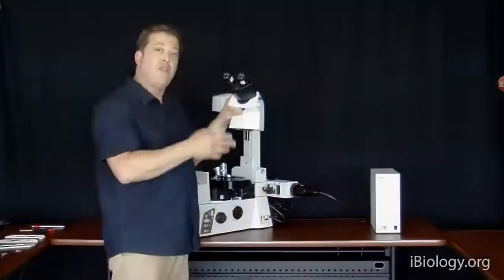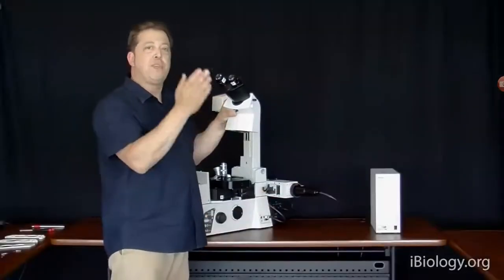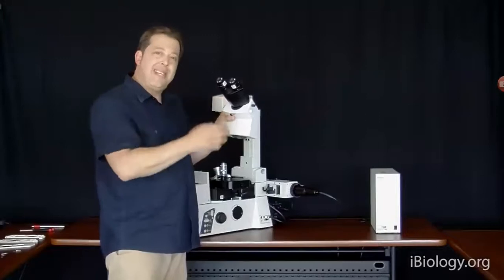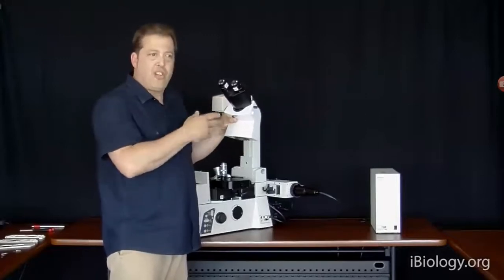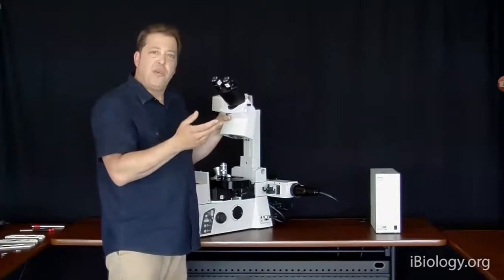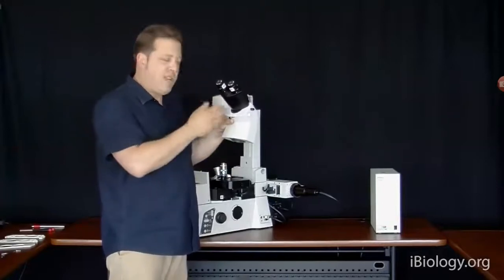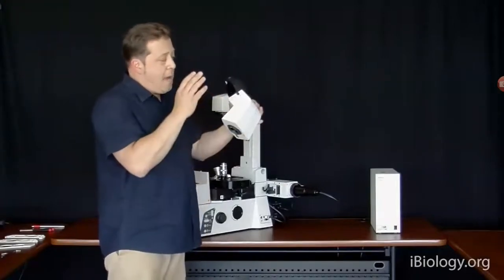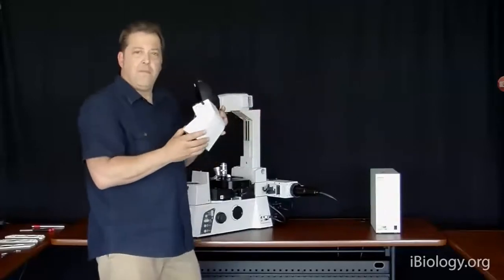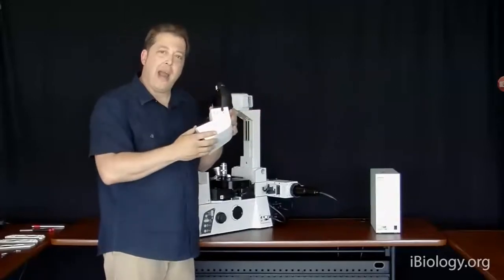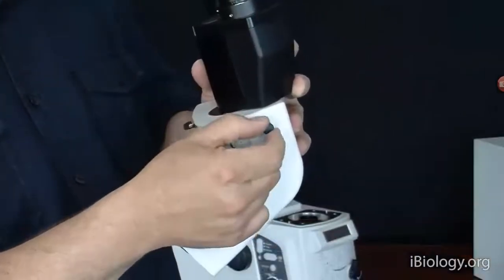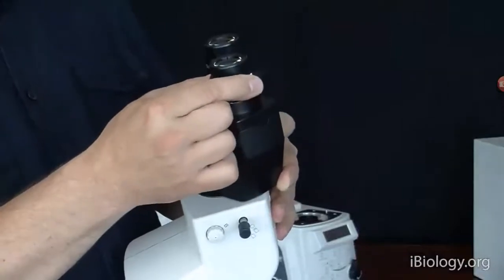And what that's going to do is allow you to look in the eyepieces and switch between, in the Bertrand position, the aperture planes of the microscope. So if you wanted to see the phase rings in the microscope or to check the alignment or adjustment of differential interference contrast, you would be able to do that by looking in the Bertrand position, or you can keep it in the open position. All objectives generally have different locations of the back aperture, so you do have a focus in the Bertrand position so that you can focus at that back aperture plane. And it's got a simple shutter to open and close the light to the eyepieces.